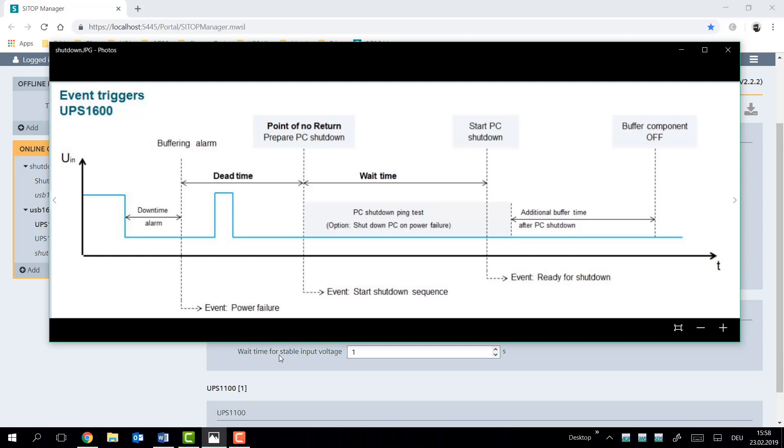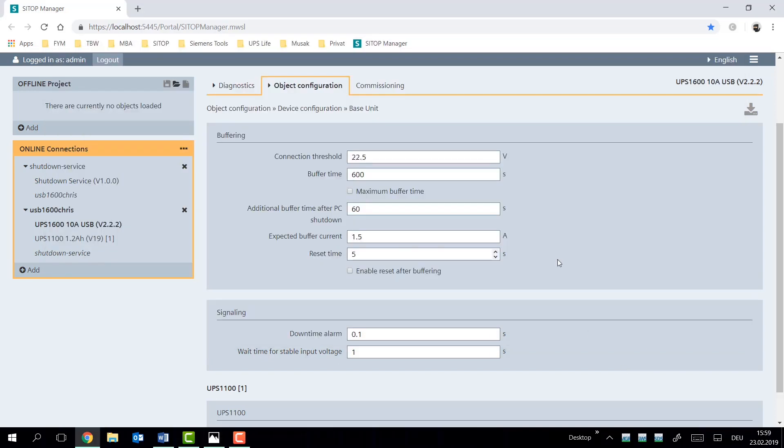The wait for stable input voltage refers to this peak here, where anything below, and its default value is one second, will not be considered as a stable input voltage in order to switch it back from buffering into the mains voltage. And with that, with those nine parameters, we have the engineering of the UPS necessary.